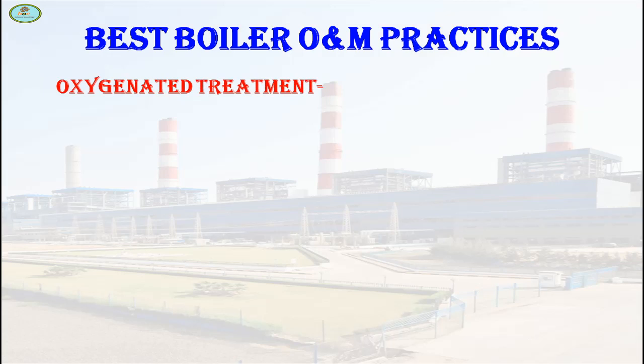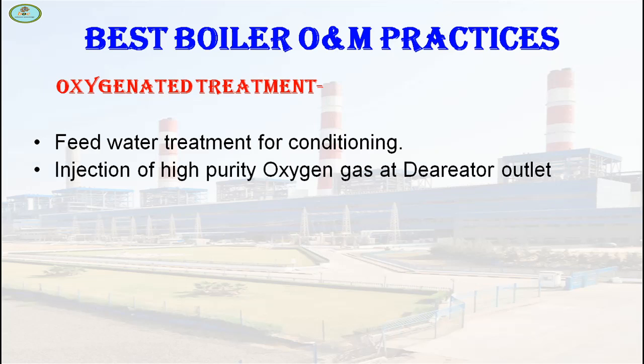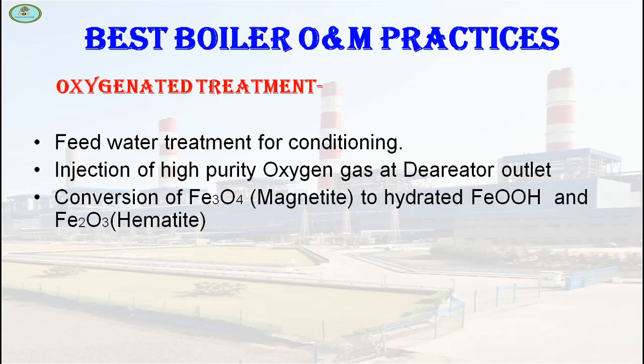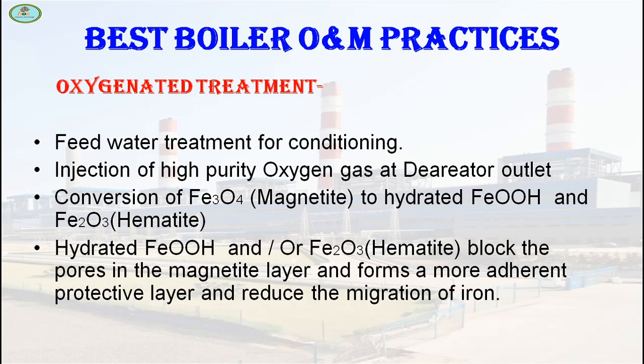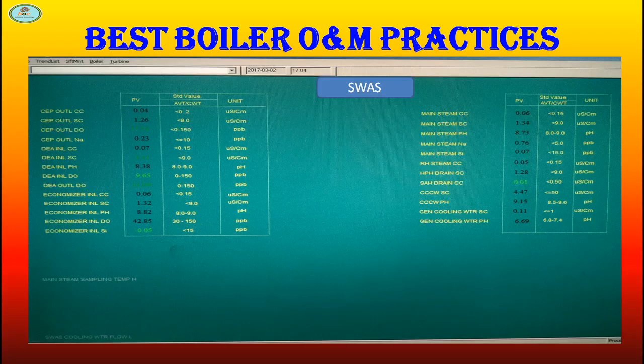Next one is oxygenated treatment. Feed water treatment is done for conditioning via injection of high purity oxygen gas at the deaerator outlet. This causes conversion of magnetite to hydrated ferric oxyhydroxide and hematite, forming a more adherent protective layer in the magnetite layer, reducing the migration of iron and preventing flow-accelerated corrosion. Regular monitoring of parameters should be done and corrective action taken if any deviation is found.